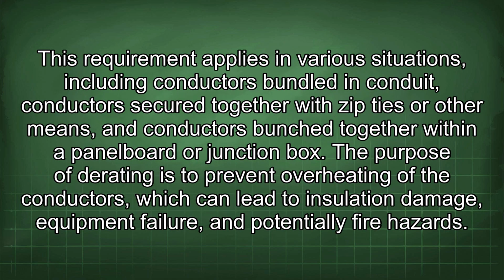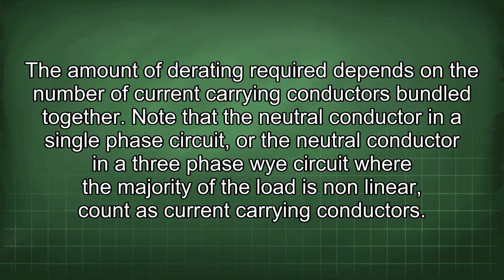This requirement applies in various situations, including conductors bundled in conduit, conductors secured together with zip ties or other means, and conductors bunched together within a panel board or junction box. The purpose of derating is to prevent overheating of the conductors, which can lead to insulation damage, equipment failure, and potentially fire hazards. The amount of derating required depends on the number of current-carrying conductors bundled together.